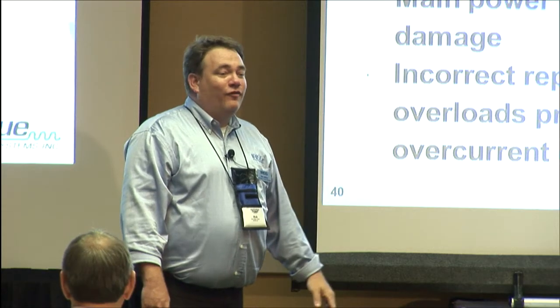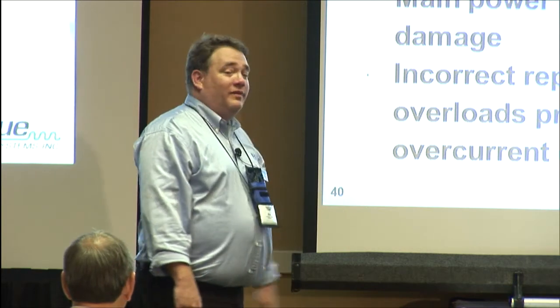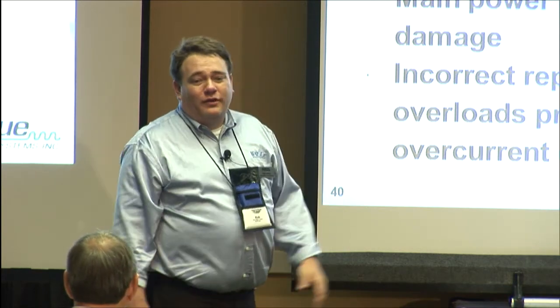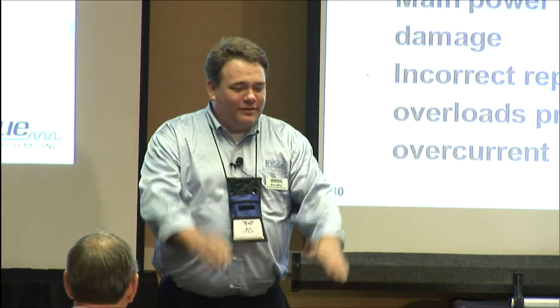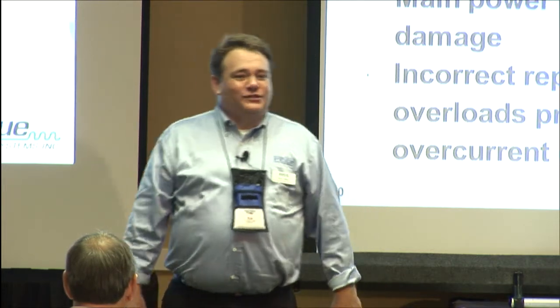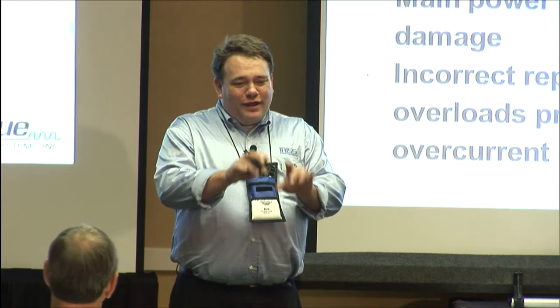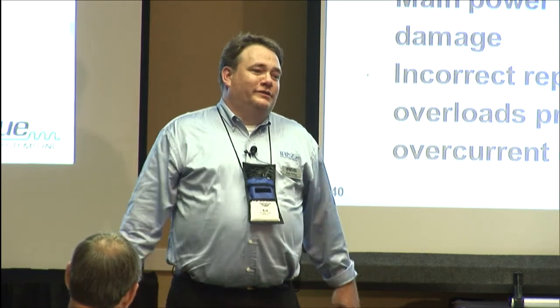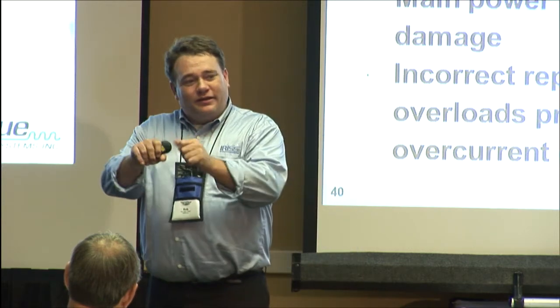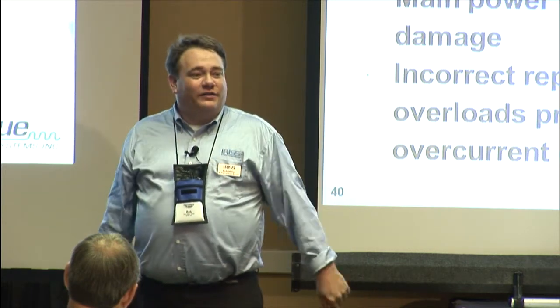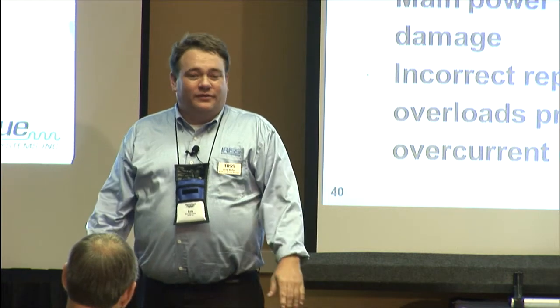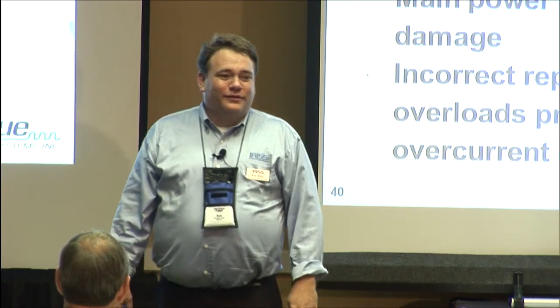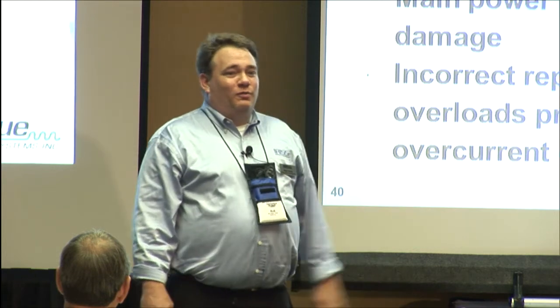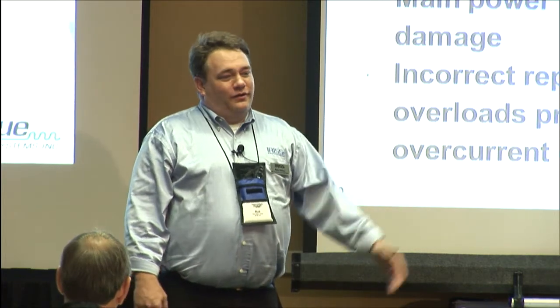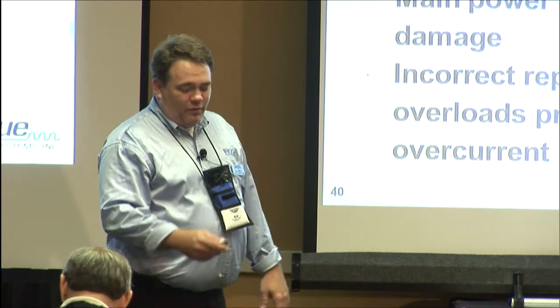That happens every day. Every single day, somebody goes to purchasing and says, we need a 200 amp breaker, we want a Square D model MC309. The purchasing agent gets on the internet and looks for the 200 amp breaker at the lowest common price. Well, it'll fit, and somebody goes back there and starts whittling away at connections so they can make it fit into the enclosure. It'll work, but it won't work well. Maybe it was 10% cheaper, but if you replace it every 6 months, you're now spending a lot of money. So building that into your program makes sense.